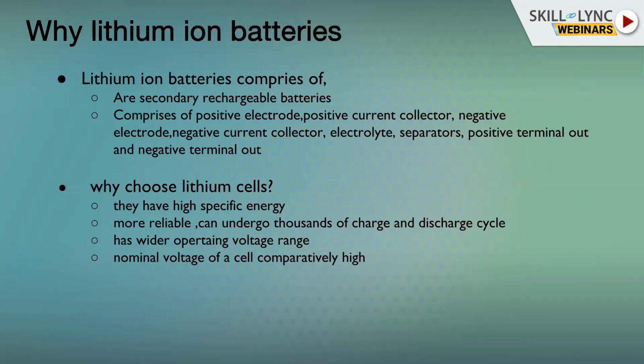The gap between the positive electrode and negative electrode is very small, as they are kept together, separated only by a very thin sheet of polythene or polymer. So if there is a very small piece of dust, how would it react? It can conduct current, and high current can flow, resulting in thermal runaway. This is one of the challenges with high energy cells.